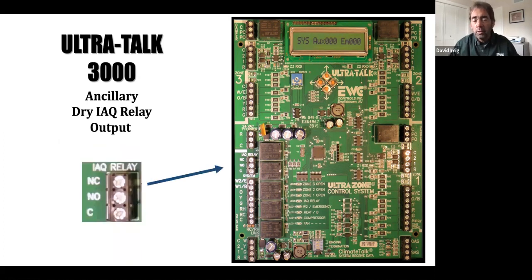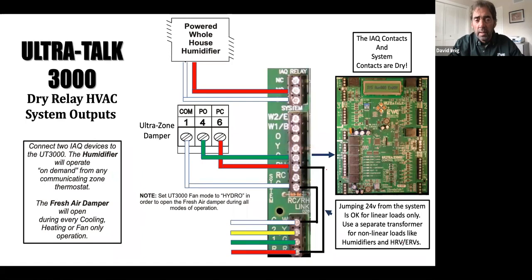Above that, the IAQ Relay. This is where I again have the option to tie in third-party IEQ products. Some examples. Here you're noting I'm tying in a whole house humidifier and an outdoor fresh air damper. Both of these need to see a demand from one of the zones and or a heating, cooling, or fan call from one of the zones.